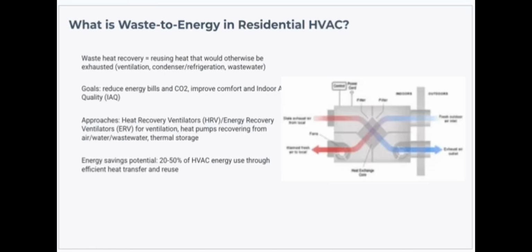What is waste energy in HVAC or residential HVAC? Waste heat recovery is reusing heat that would otherwise be exhausted: ventilation, condenser/refrigeration, wastewater. The goal is to reduce energy bills and CO2, and improve comfort and indoor air quality. The approaches are HRVs and ERVs for ventilation, heat pumps recovering from air/water/wastewater, and thermal storage. The energy savings are potentially around 20 to 50% of HVAC energy use through efficient heat transfer and reuse.